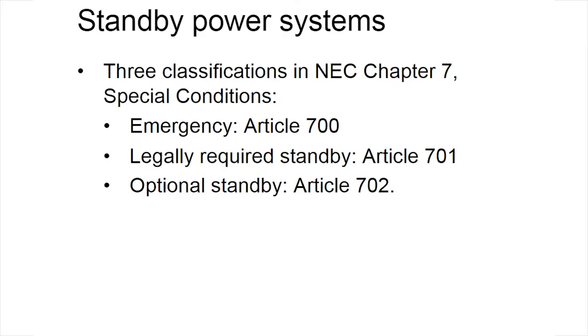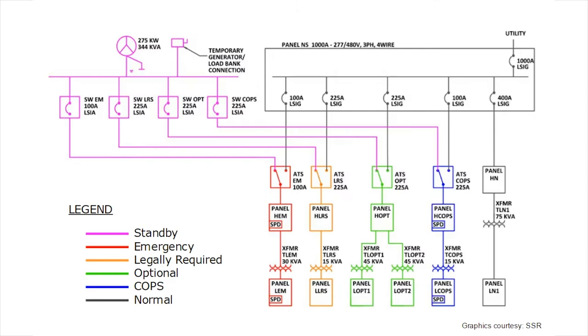Now we'll start our look at emergency systems with a look at the three classes of standby systems. The NEC describes three types for a general facility, that is, for a facility that doesn't fall under the requirements of one of the other articles, like COPS, Critical Operations Power System, or healthcare, which would fall under 517. Article 700 covers emergency systems, 701 covers legally required standby systems, and that's a term that we'll define more clearly later. And Article 702 covers optional standby systems. And we'll use this diagram to discuss some of the aspects of each of the systems.